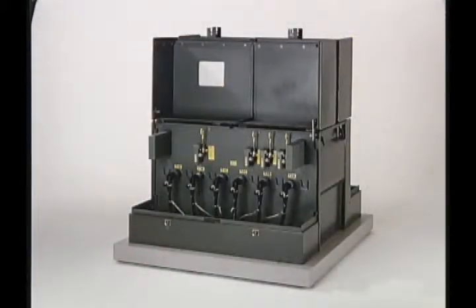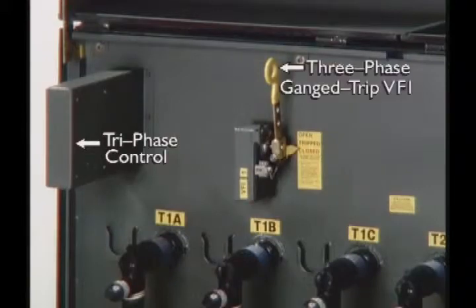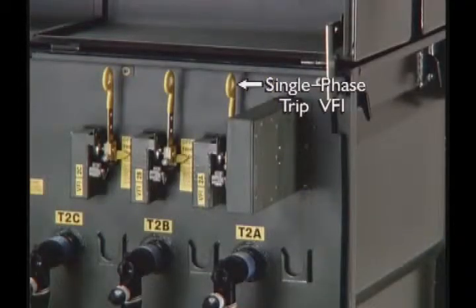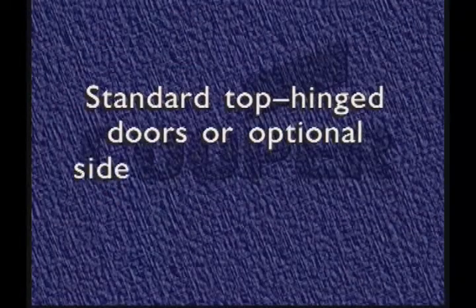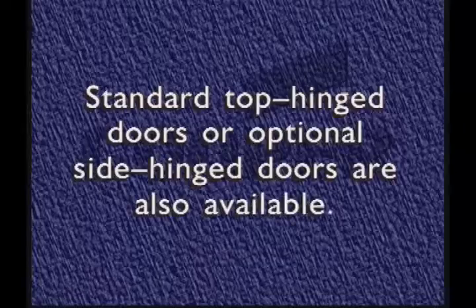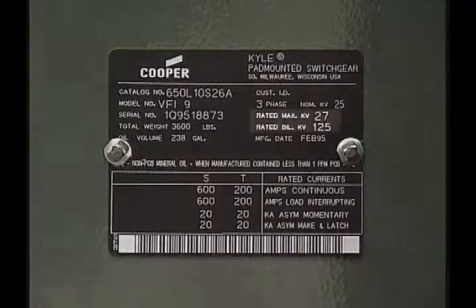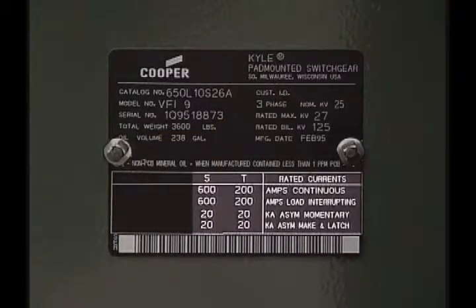The tap side includes the tri-phase control, three-phase gang trip VFI, single-phase trip VFI, and bushing wells. Standard top hinge doors or optional side hinge doors are also available. The nameplate specifies the voltage and current ratings of the unit.